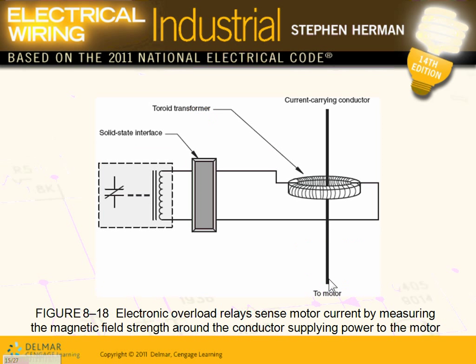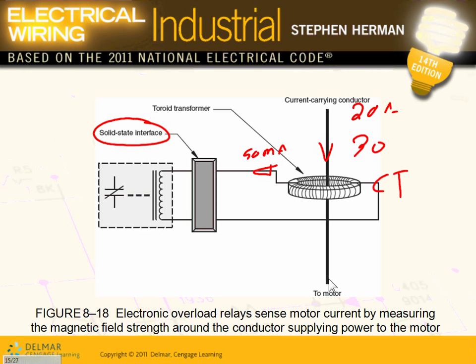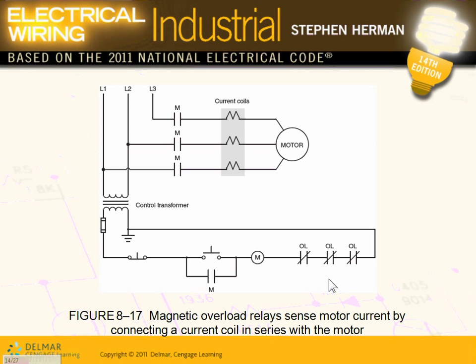That's your magnetic overload. The second one is electronic: I'm supposed to get 20 amps, it moves to 30 amps. When you hit 30 amps, the CT — current transformer — picks it up and converts it to, say, 50 milliamps. That signal goes into an electronic solid-state device, which analyzes it and makes a decision to open the contact that controls the flow of power to the control circuit of the motor.